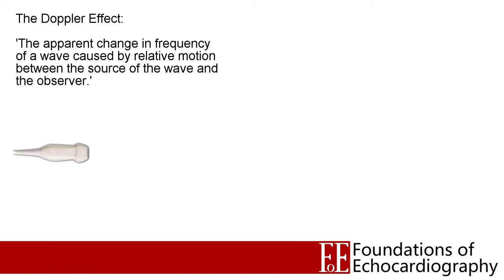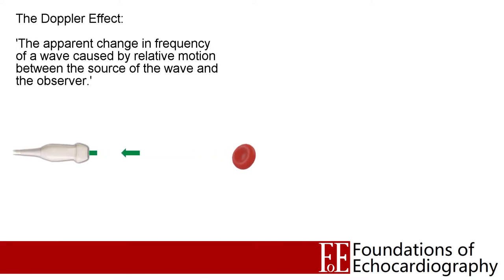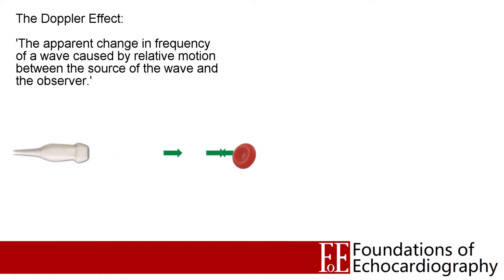Here the observer is our transducer, and the source of our wave is our reflective surface — in this example, a red blood cell. Now if there's no relative motion between these two, if they're at a fixed distance apart, then the wave that leaves the transducer and strikes the red blood cell will be reflected back towards the transducer with an identical frequency. We can imagine that each of the green arrows represents the peak of one wave, spread evenly apart, returning equally evenly spaced when they come back to the probe.